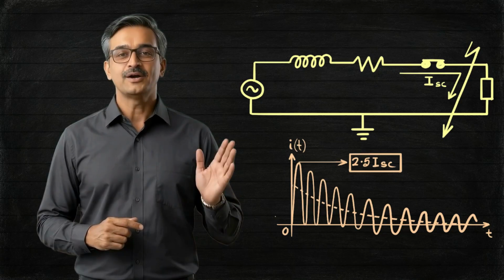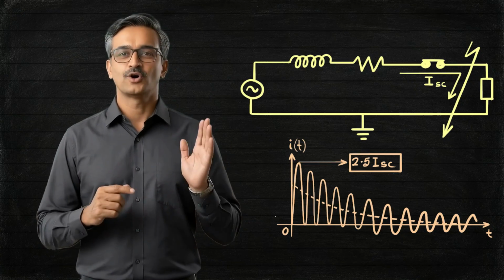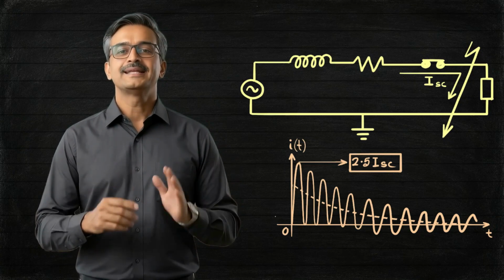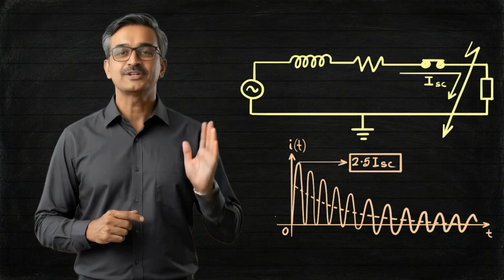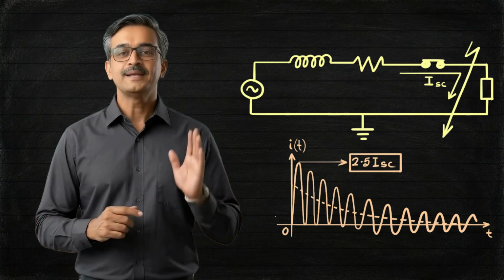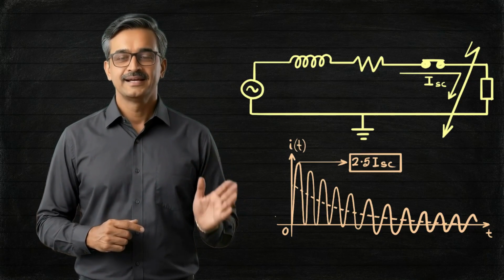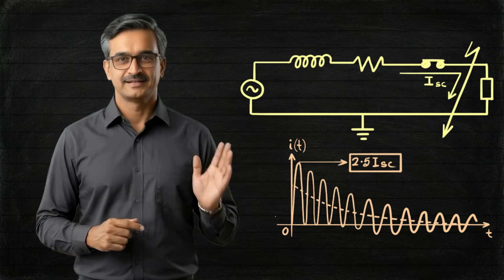Once the circuit breaker closes under the fault condition, the short circuit becomes fully established in the system. Immediately, the protection relay senses the fault and sends a trip signal to the circuit breaker. The circuit breaker then starts its opening operation. However, this entire process requires a small amount of time before the commencement of contact separation. The high making current, which reached its peak during closing, was only a transient phenomenon.